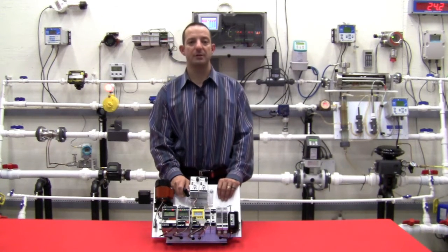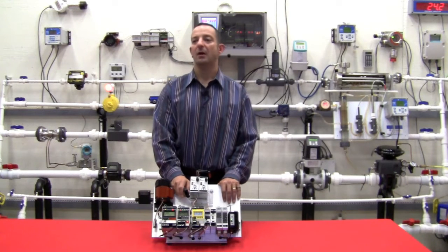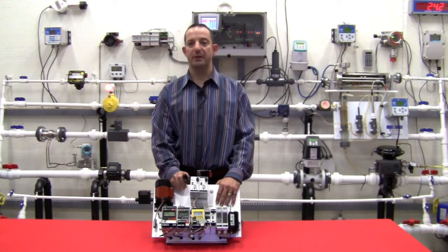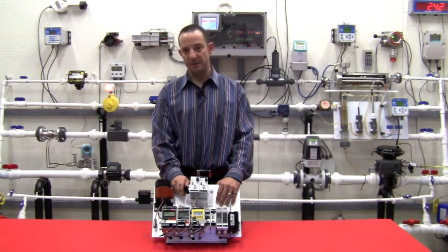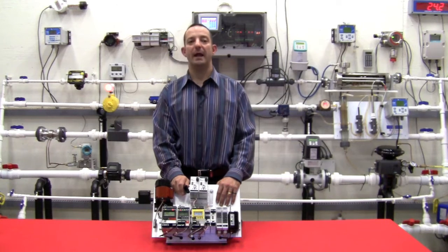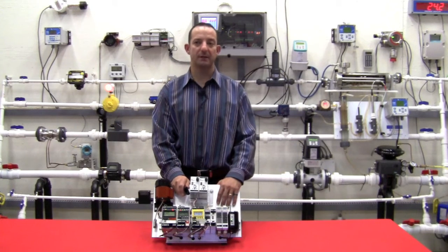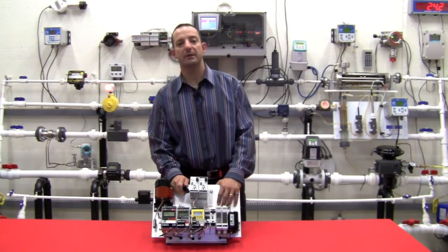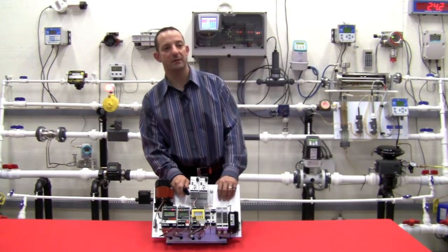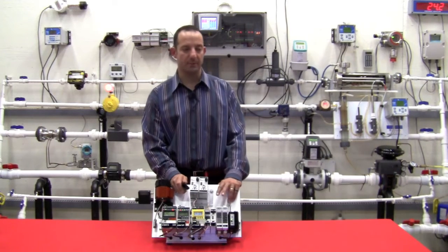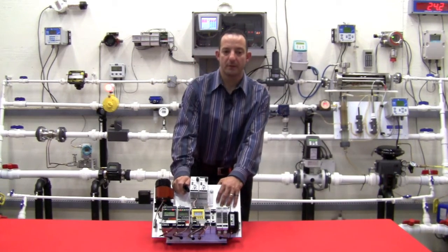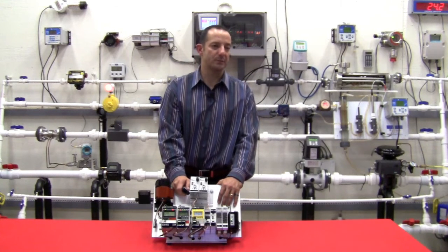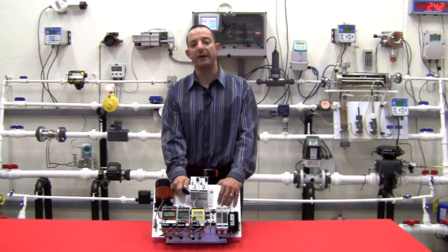To do that same function on a PLC or a DCS often involves getting onto the card and making adjustments, or going into the PLC program itself and calibrating or adjusting the calibration coefficients on the card. Typically, those devices are not designed for easy interface to do something like that, but the temperature transmitters are. So there's 7 reasons that you can give your customer as to why temperature transmitters might be preferable over direct wiring.